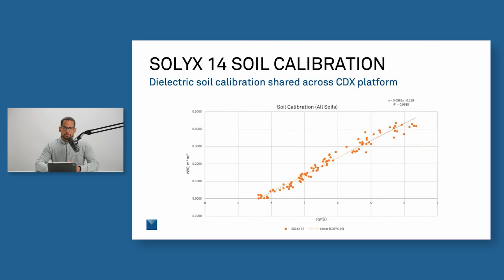So this is great. Now we get an accurate measurement of dielectric permittivity, but ultimately we need to take that dielectric permittivity measurement and convert it to a water content. Here you see the calibration equation we've developed for the entire CDX platform. Because we now have tools to accurately estimate the dielectric permittivity, we can develop a singular equation that can be used across the CDX platform.